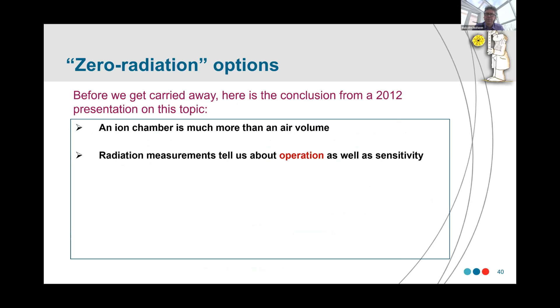But, again, always a but. There was a presentation on this from 2012. We have to realize that an ion chamber is more than an air volume. And one of the things that an end user gets from a calibration laboratory is confidence. We're not really selling a calibration certificate as a calibration laboratory. What we're selling is confidence that the detector that the user has will work, and if you use this calibration certificate, you will get the right answer. We're predominantly providing a confidence in operation.